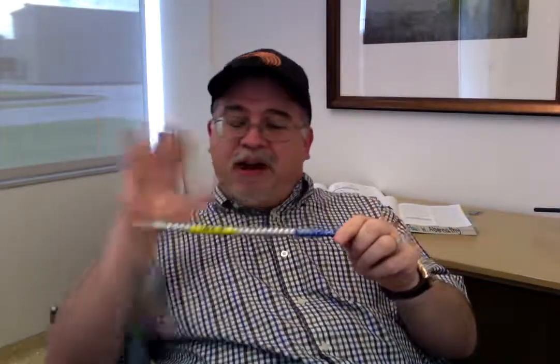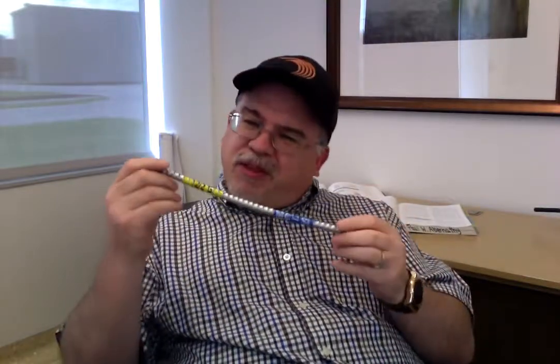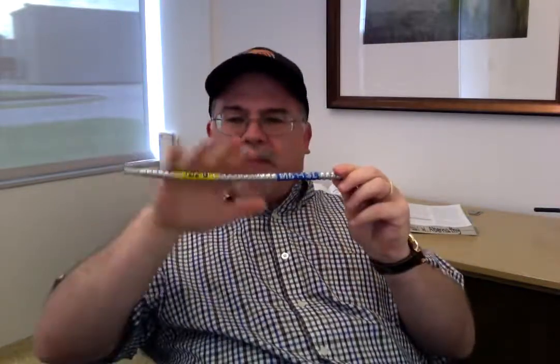So if it's installed in the walls and it temporarily gets some rain or moisture on it and it doesn't really saturate it or get submerged through flooding, because if it's a flooding condition, you need to refer to the NEMA document for water damaged electrical equipment, and that's going to give you some guidance on what to do with this cable when it gets submerged or the ends get wet. But for the surface here, water simply going over it is not going to affect this product. And again, the conductors inside of it are rated for wet location, so we feel confident with that.